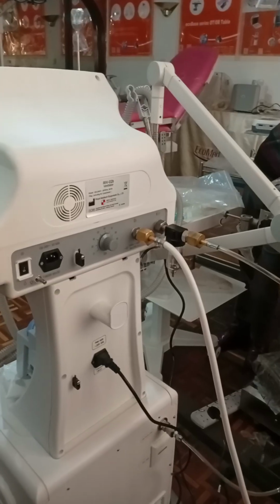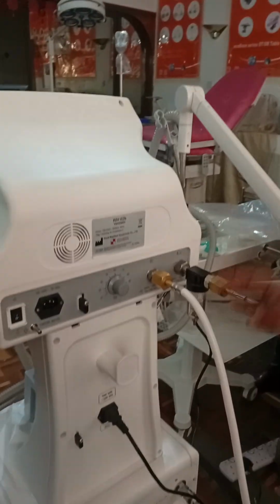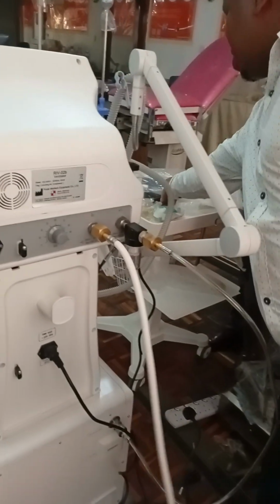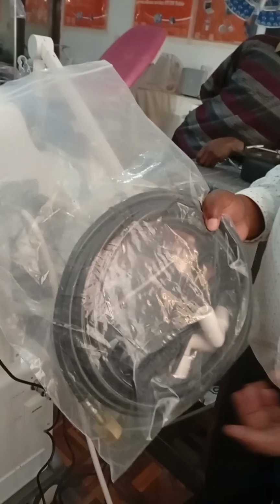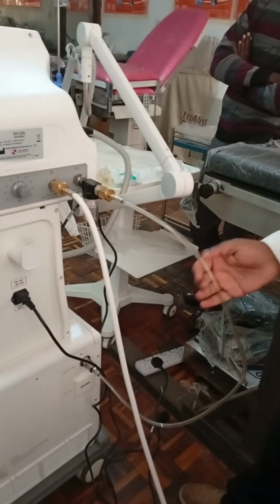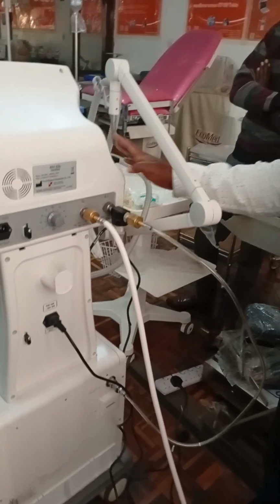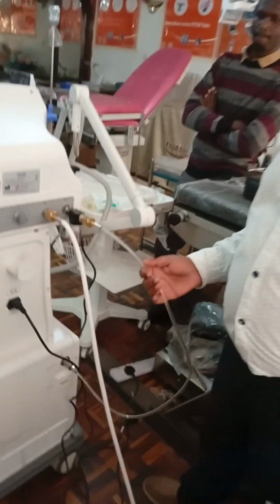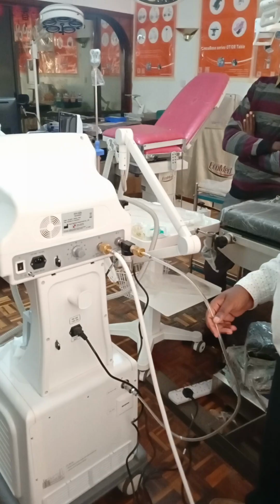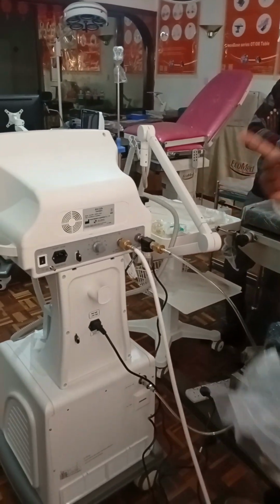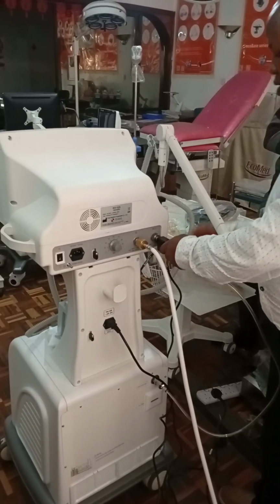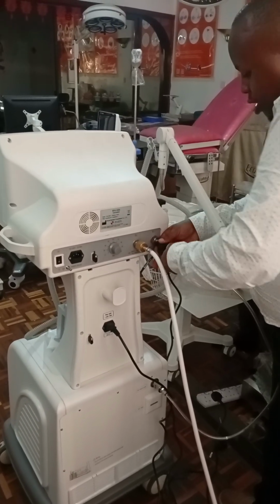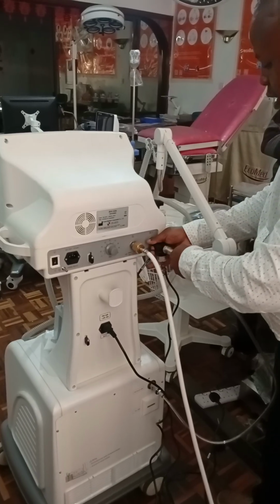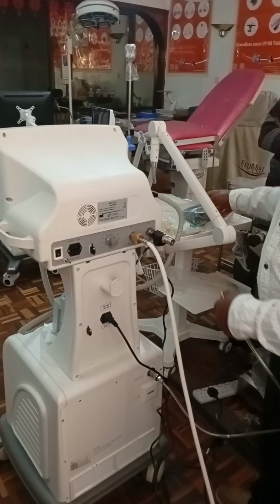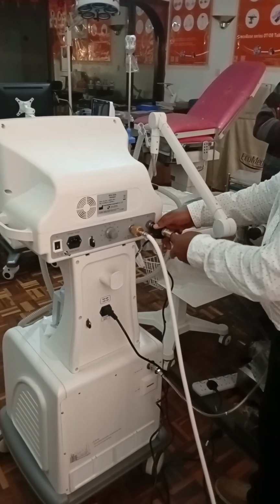Our machine comes with two pipes. One for the oxygen, this white one. We also have this black one for the medical air. If you already have piped medical air, you will not need to connect this one. This one is a connection between our compressor and our ventilator. The reason we are connecting this is in case you don't have the medical air, you'll be able to use this. So in a situation whereby you have the medical air in the facility and you don't need our compressor, you have to disconnect this clear pipe here, and then you connect this black pipe here.